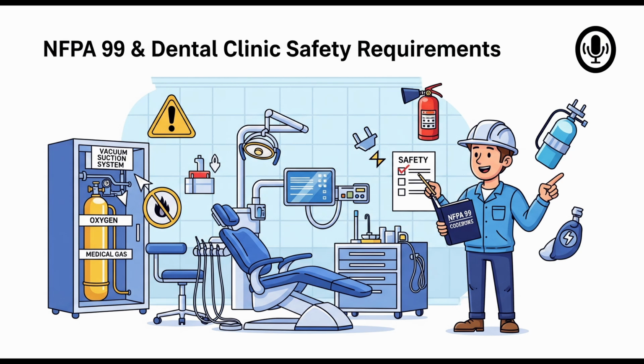Let's start at the source, the equipment making the air or vacuum, so compressors, pumps, maybe cylinders. For Category 3 medical gas source equipment, Section 5.3.3.6.11 gives a pretty significant allowance. Oh yeah, what's that? It says components like the medical air compressors, the dryers, aftercoolers, filters, regulators, they're permitted to be simplex. Simplex, you mean just a single unit, no automatic backup required?